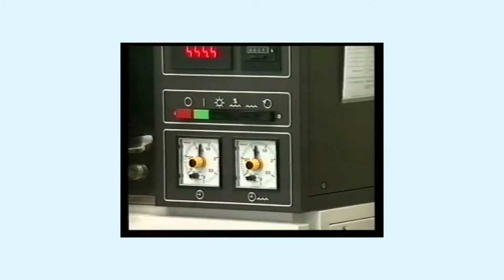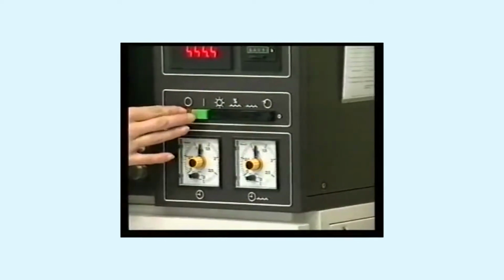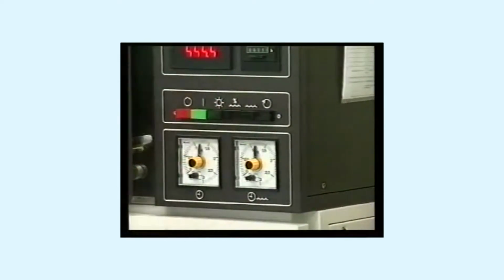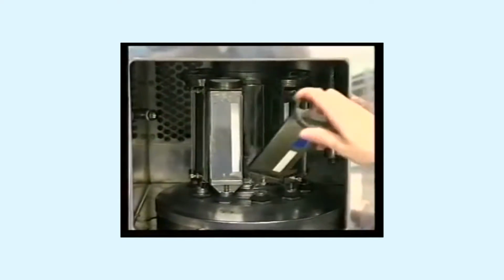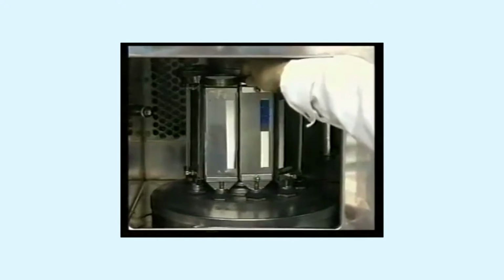The conditions of temperature and humidity inside the test chamber are set. The specimen holders are mounted on the rotating table until all positions are filled. The holders rotate around the central light source. For every revolution of the table, the holders rotate through 180 degrees.